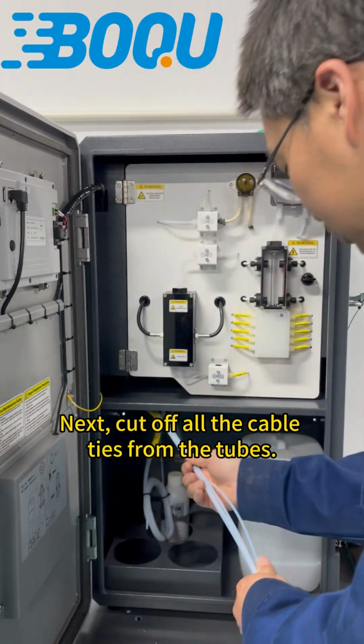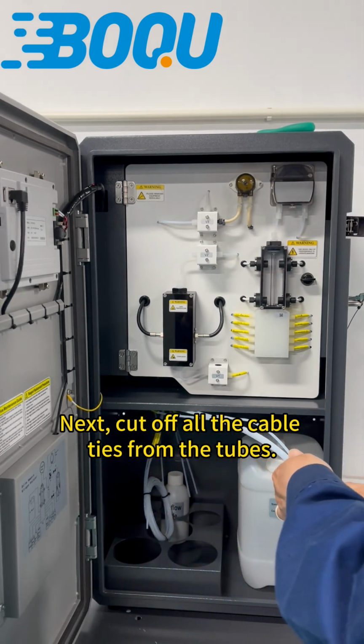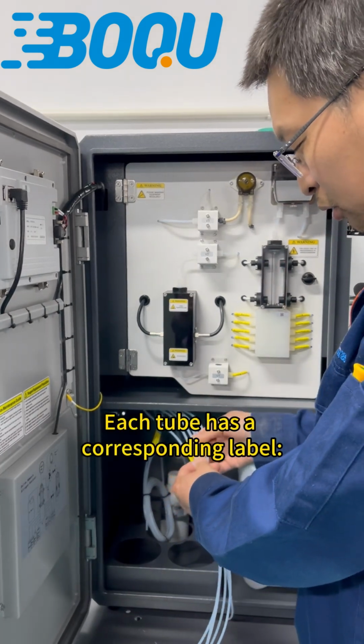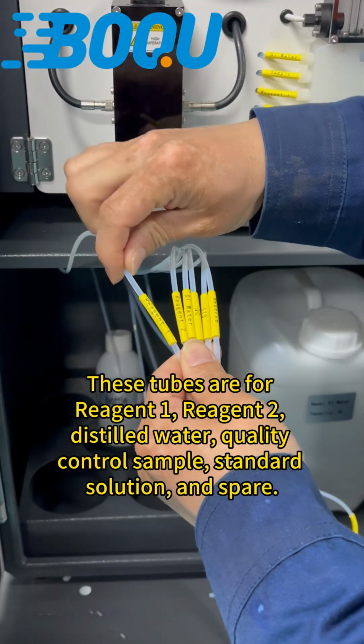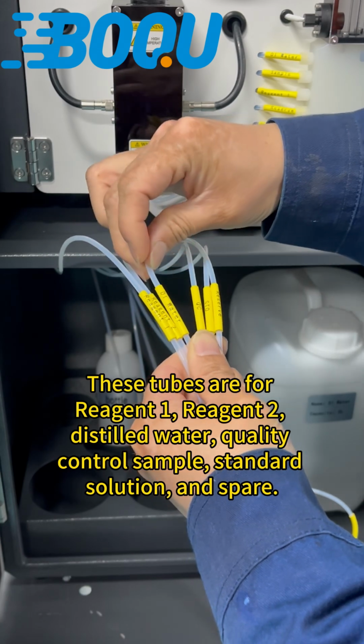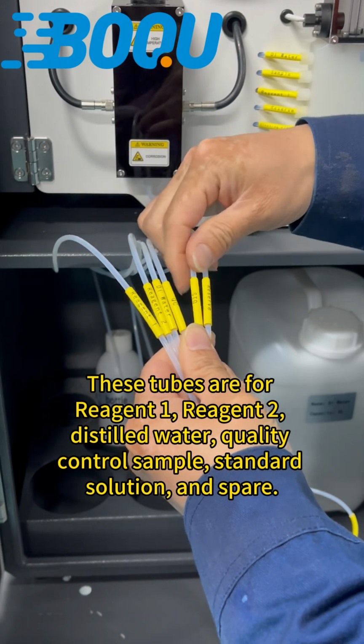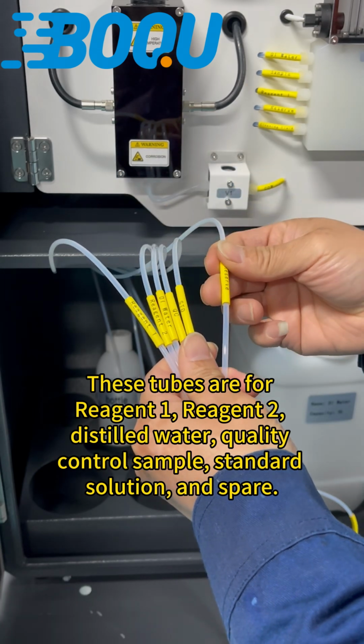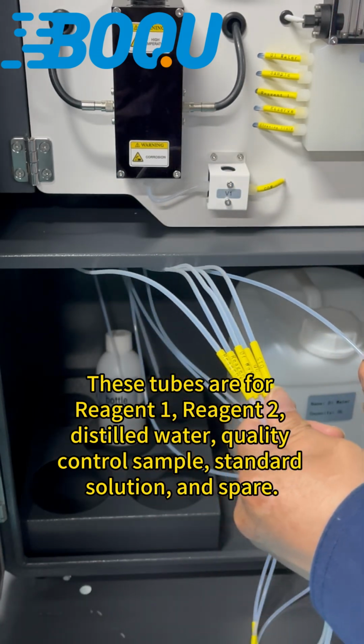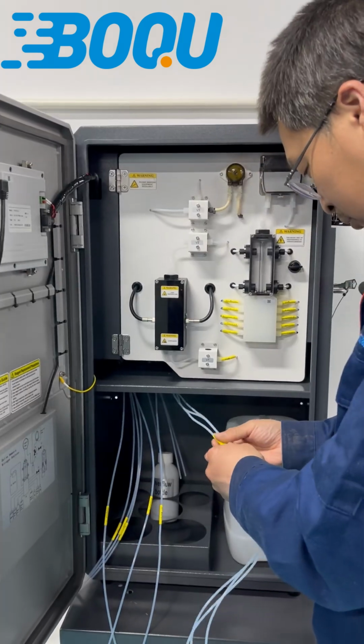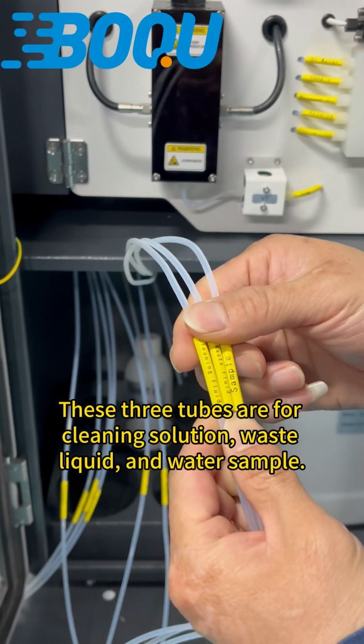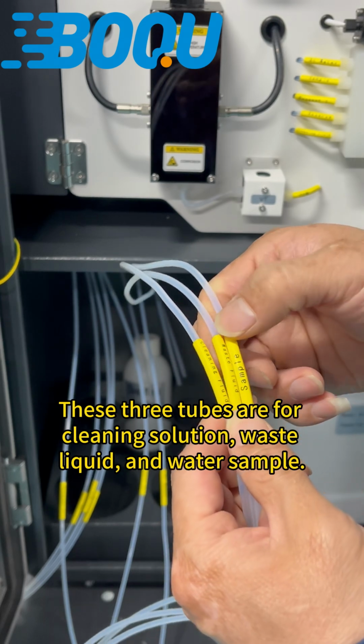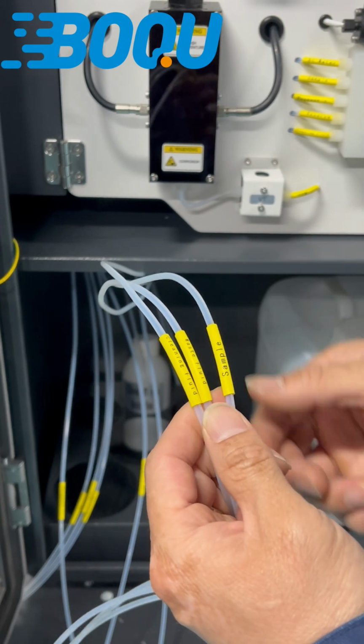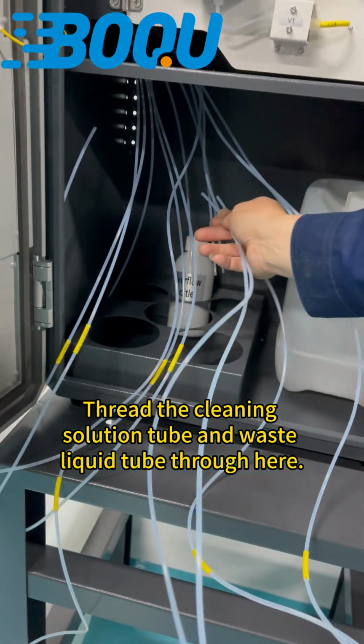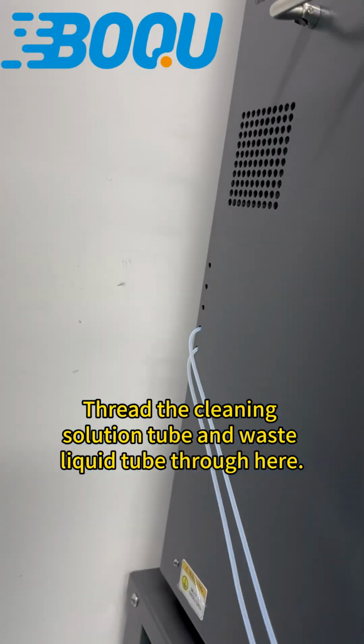Next, cut off all the cable ties from the tubes. Each tube has a corresponding label. These tubes are for Reagent 1, Reagent 2, distilled water, quality control sample, standard solution, and spare. These 3 tubes are for cleaning solution, waste liquid, and water sample. Thread the cleaning solution tube and waste liquid tube through here.